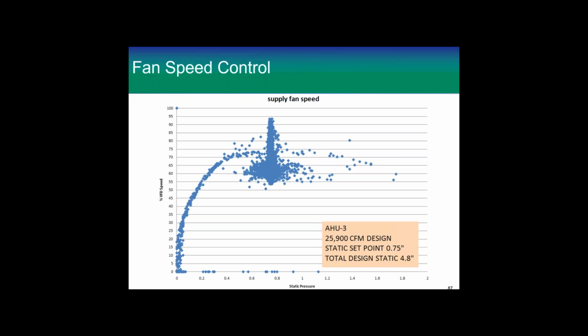All right. So here's an example of the old-fashioned way we did it before we started doing this, and why it's a problem. The balancing contractor set this fan. This is an actual fan. This is the trend data for a static set point of 0.75. That's the static set point. Total design for the whole system, internal and external, was 4.8.